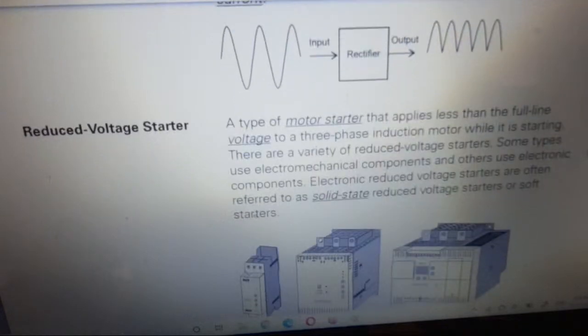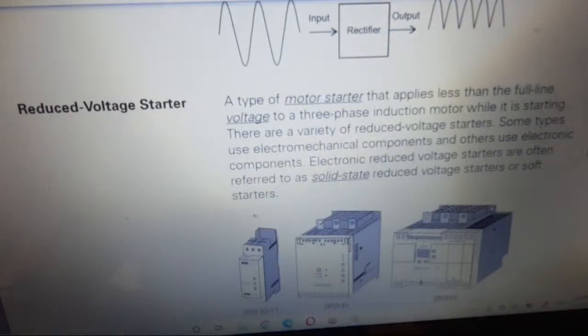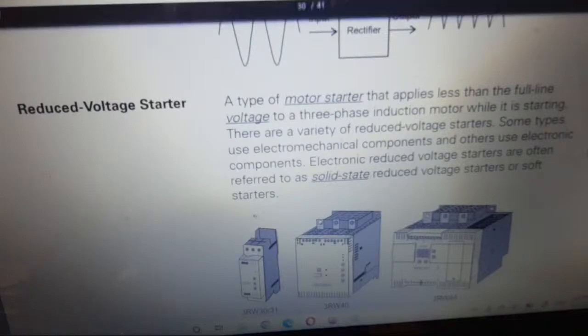Reduced voltage starter, a type of motor starter that applies less than the full line voltage to the three-phase induction motor while it is starting. There are a variety of reduced voltage starters. Some types use electromechanical components and others use electronic components. Electronic reduced voltage starters are often referred to as solid state reduced voltage starters or soft starters.